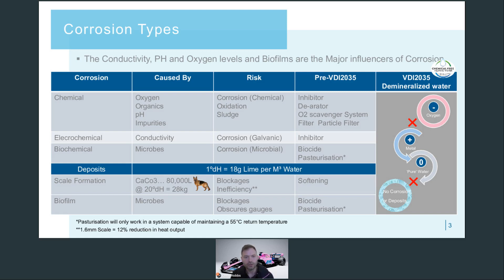Salt regenerative softening is a way that we can remove this hardness, but salts used within that process increase conductivity, leading to electrochemical corrosion problems I mentioned earlier. The solution again is to use pure demineralized water, as the demineralization process eliminates the hardness. Biofilms can also cause deposits. Sludgy, slimy colonies of bacteria grow even in oxygen depleted environments, and these clog everything up. They can be a real problem in low heat systems, which are a perfect temperature for the bacteria to thrive in. But again, do we really want to use biocide and expensive killer chemicals to deal with that issue?